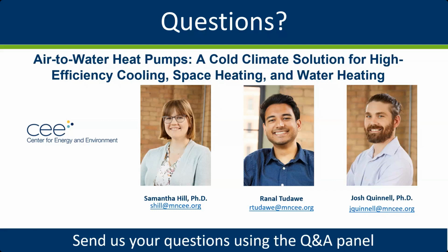I do think though that there's probably specialized equipment that's focused on that operating range that will be much better than these all-purpose systems that we studied here. I know in the previous project that we were looking at some air-to-water systems for pool heating that convincingly were claiming their COPs were 5 or 6 for heating pool water, which has a lot of savings compared to conventional pool heaters, which are going to be at either combustion efficiencies or electric resistance efficiencies.